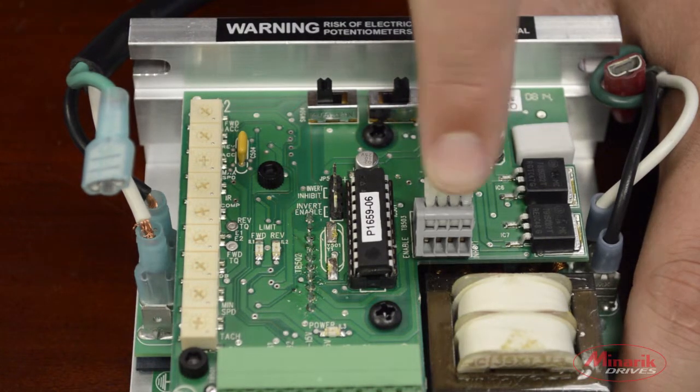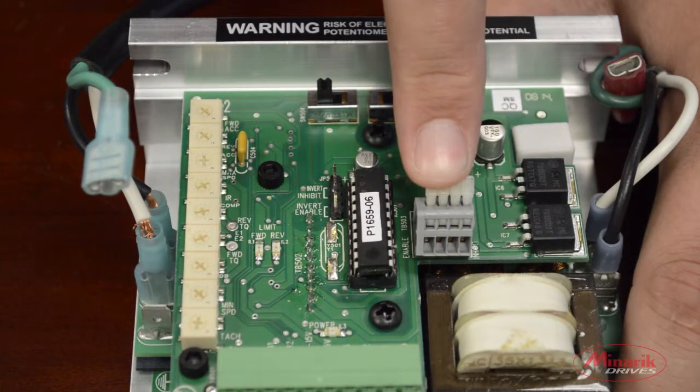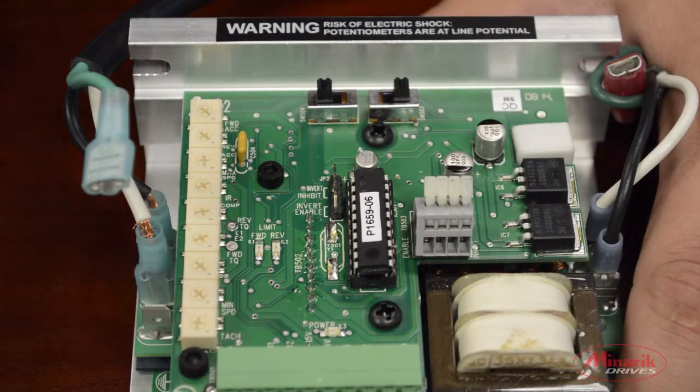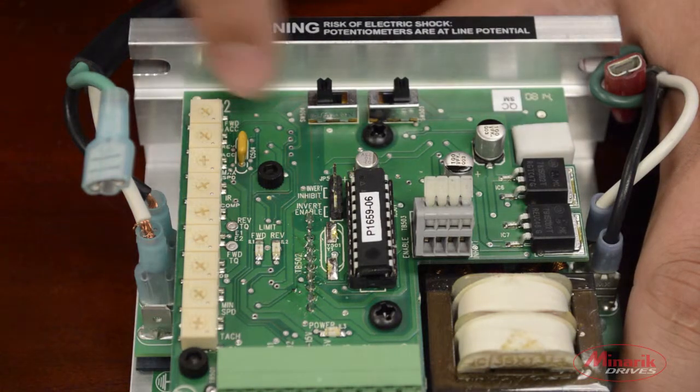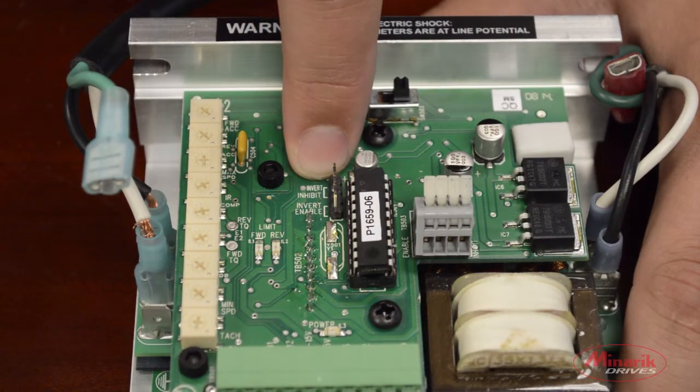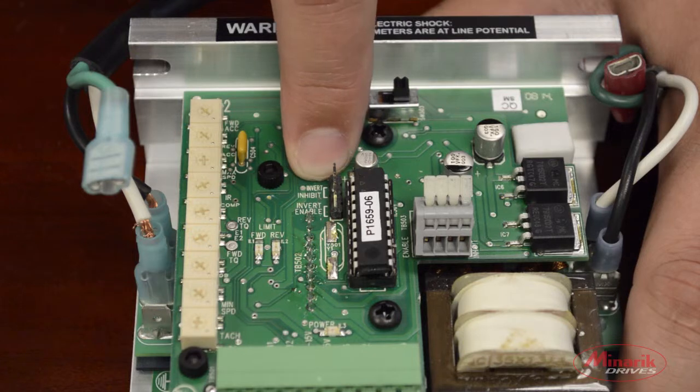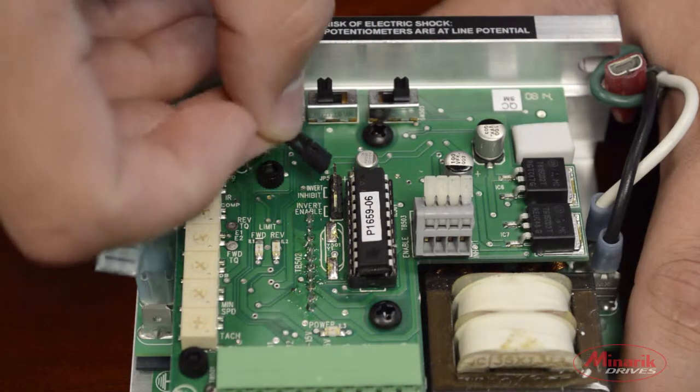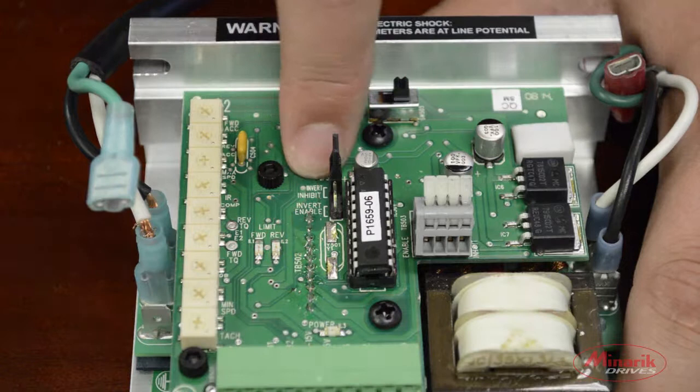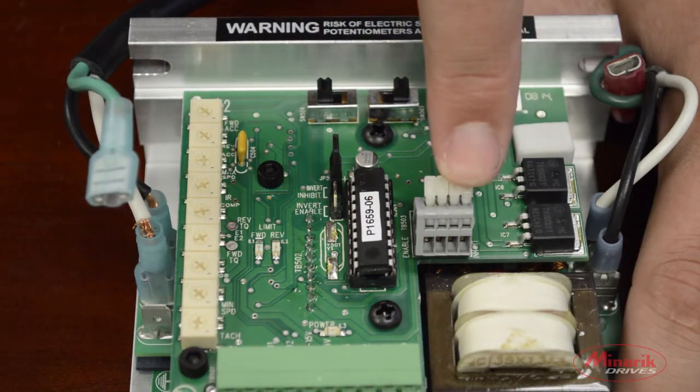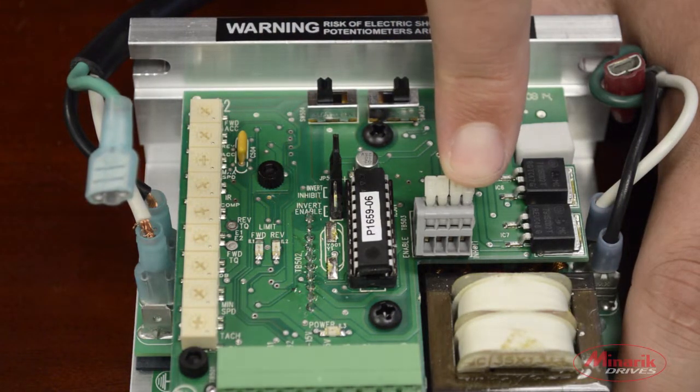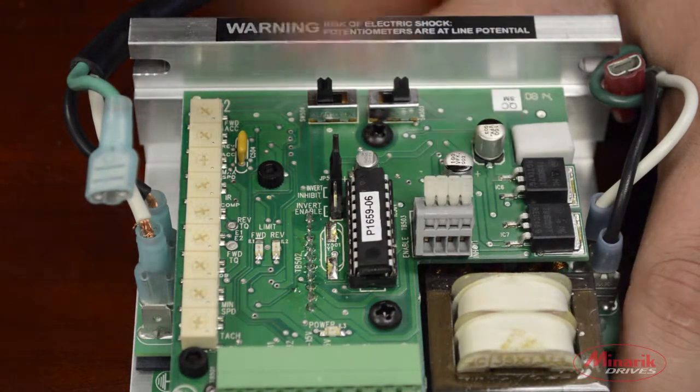This is the same with enable. To invert these settings, simply jumper the two leads located here in the middle of the drive. The first two leads are for inhibit. This activates invert inhibit, where when these two terminals are open, the drive will activate inhibit.